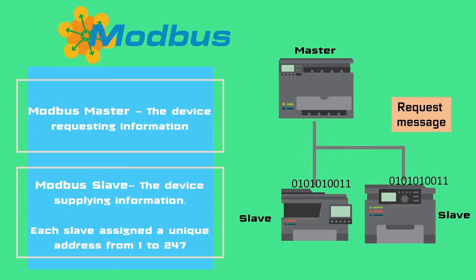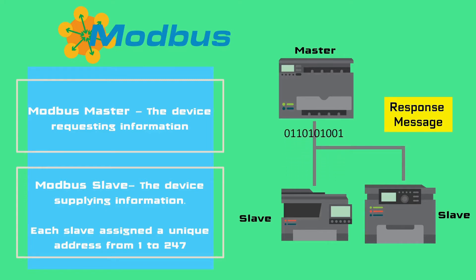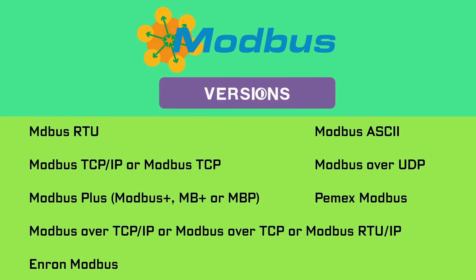The device requesting the information is called the Modbus master and the devices supplying information are Modbus slaves. Each slave is assigned a unique slave address which could be from 1 to 247. In addition to requesting information from slaves, the master can also write information to the slaves. Modbus is typically used to transmit signals from instrumentation and control devices to the main controller or data gathering systems like PLC, DCS, or SCADA. Multiple versions of Modbus protocols have evolved with changing technological requirements.